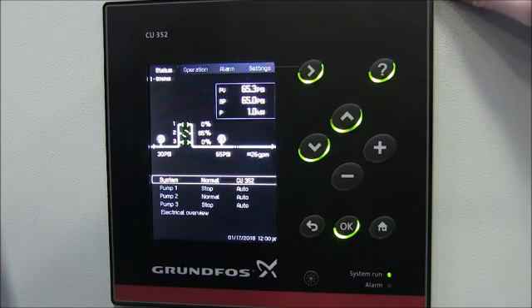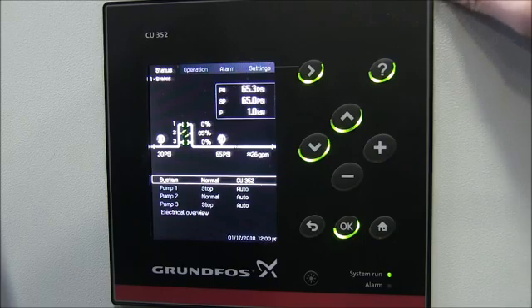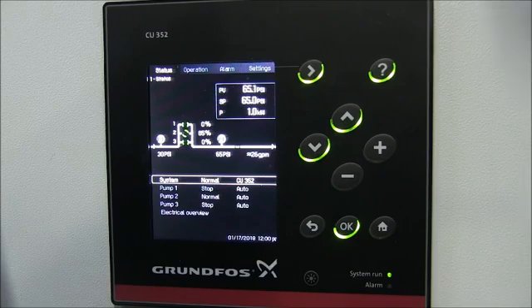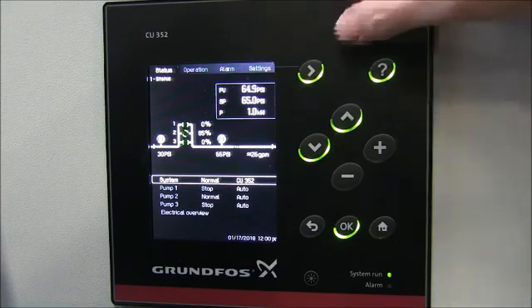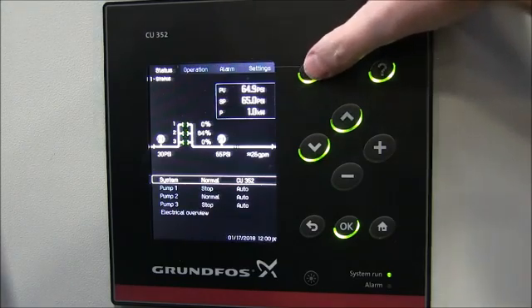The intent of proportional pressure is to reduce the energy at low flow by outputting a lower pressure, because that higher pressure is not needed since we have less friction in our piping.